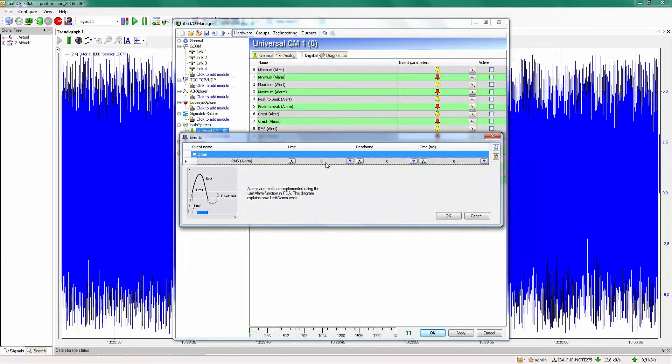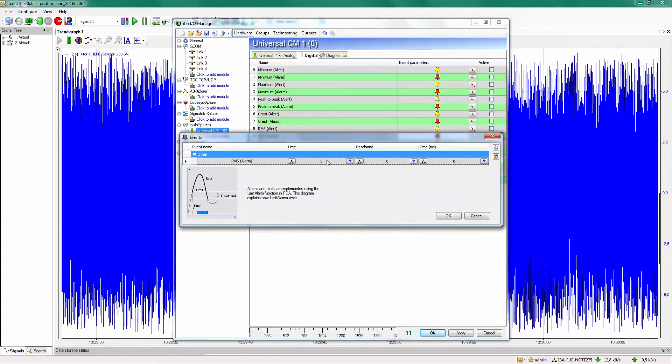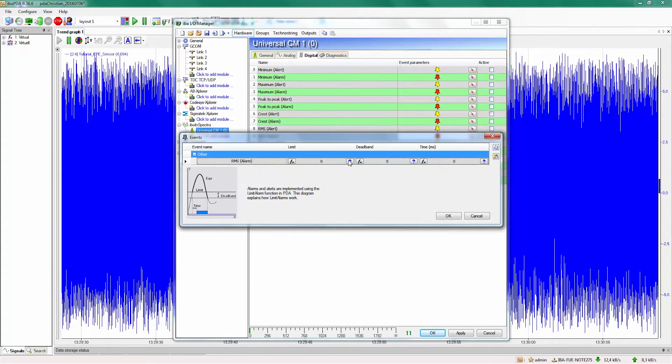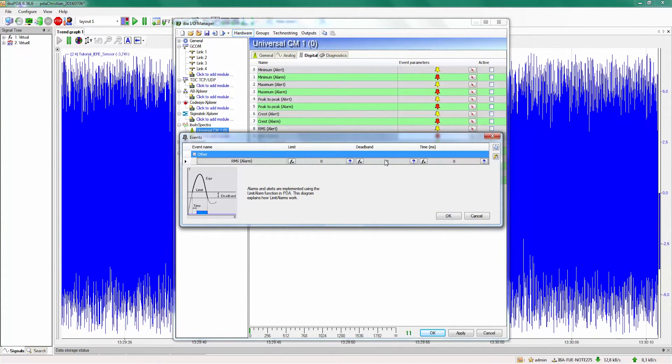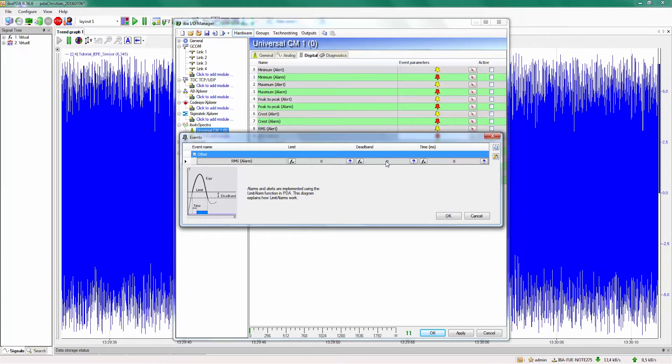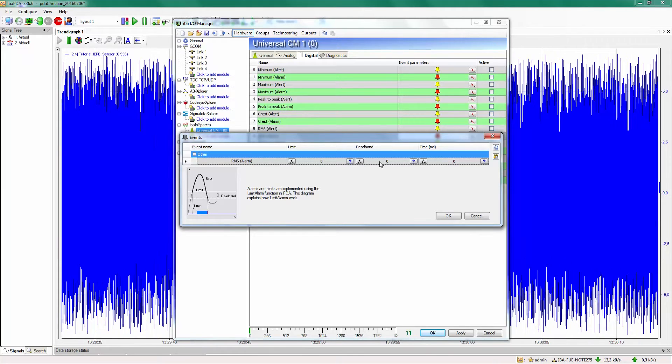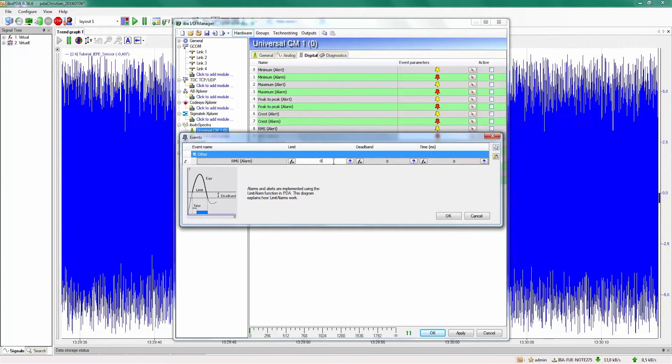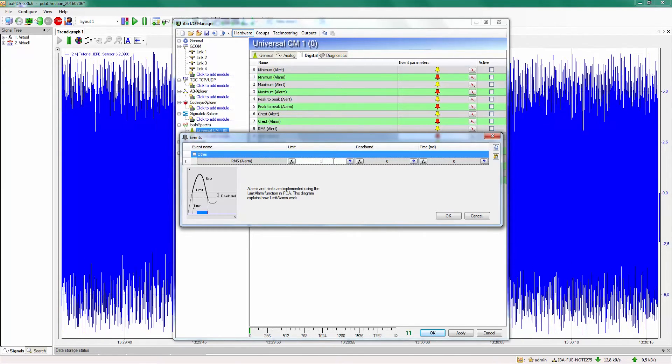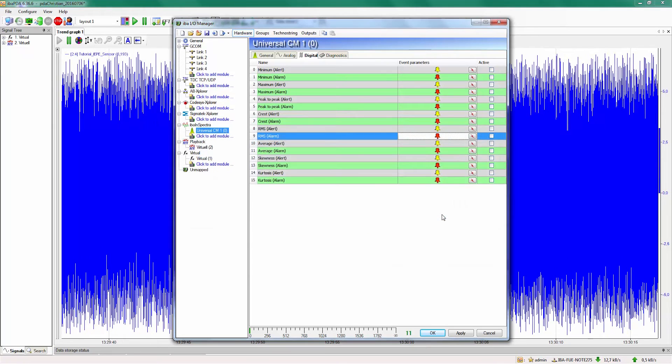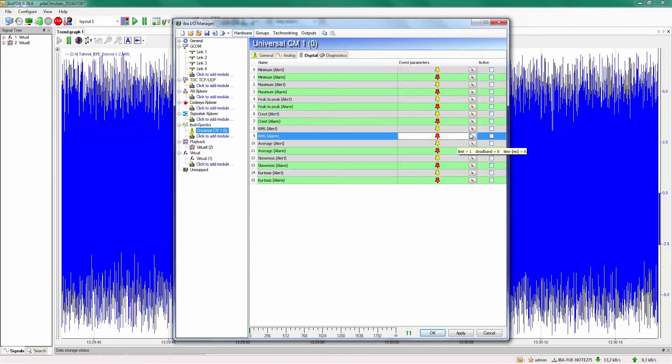We just open the alarm settings where we can enter a limit or a threshold, a dead band and a delay time. In our case a limit will be ok, we confirm this and now we have to activate this alarm.